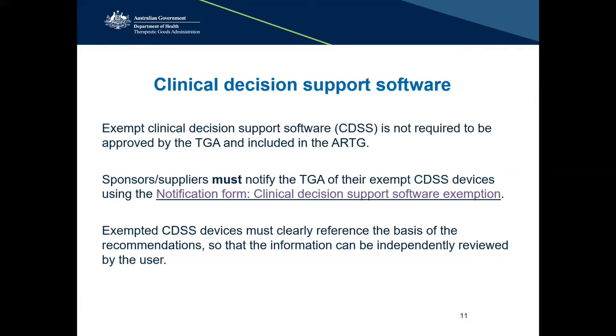Although the products that are covered by this exemption are not required to be included on the ARTG, we have included a requirement that sponsors of these products notify the TGA. By sponsor, we just mean people who are supplying these products into Australia, so it could be the developers or anything like that. We have a notification form, and this is quite different to applying to put something on the ARTG. The notification form is very basic. It just has some contact information and a brief description about the product. And the other key thing is it's a notification, so it doesn't get any kind of formal approval by the TGA. It's just a means for us to be able to track who is using this exemption.